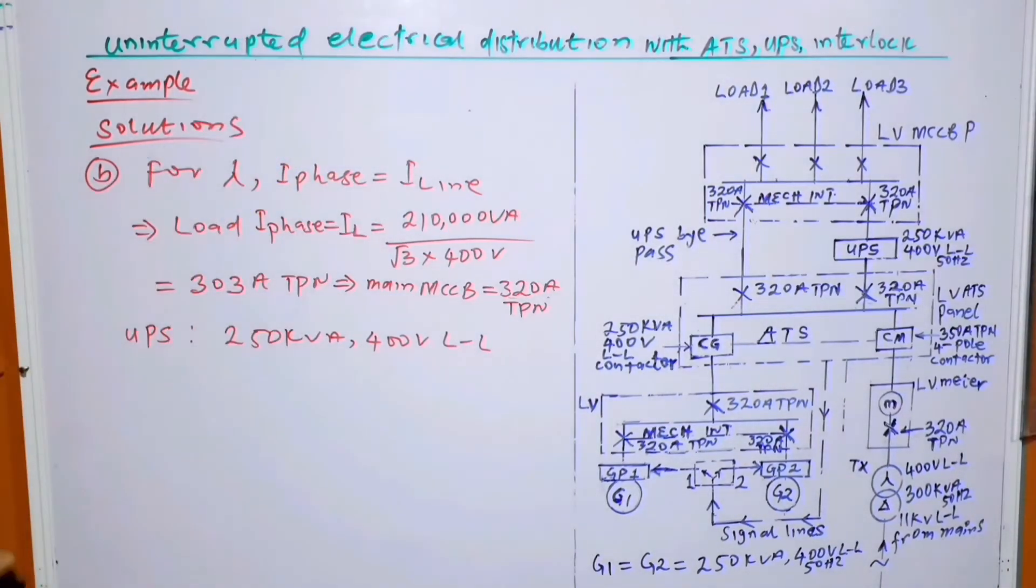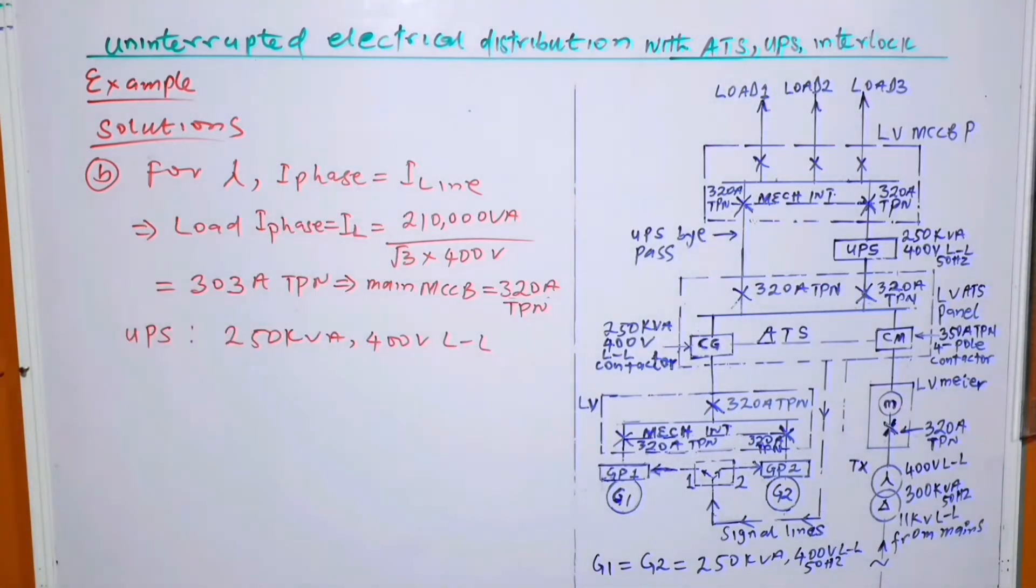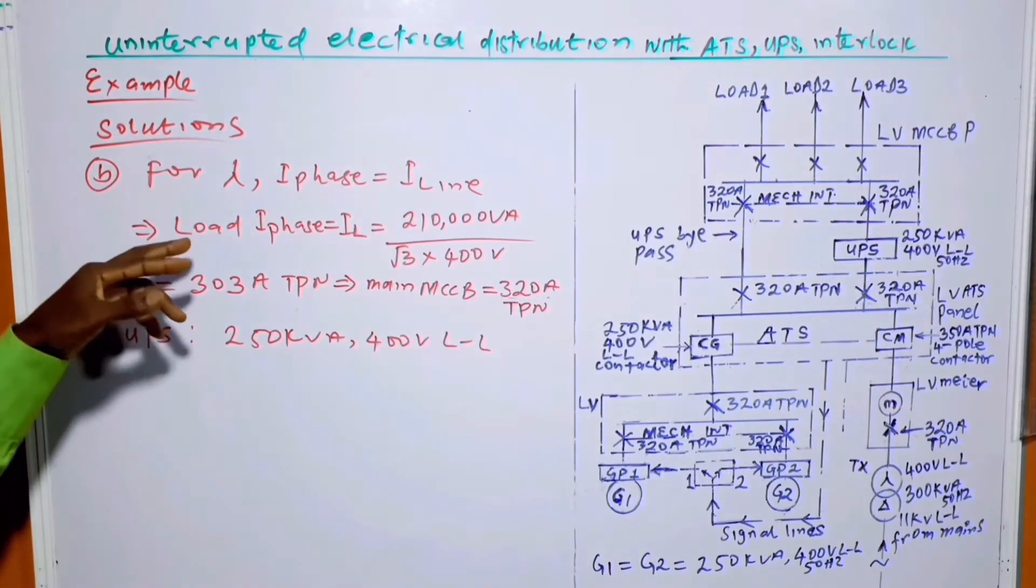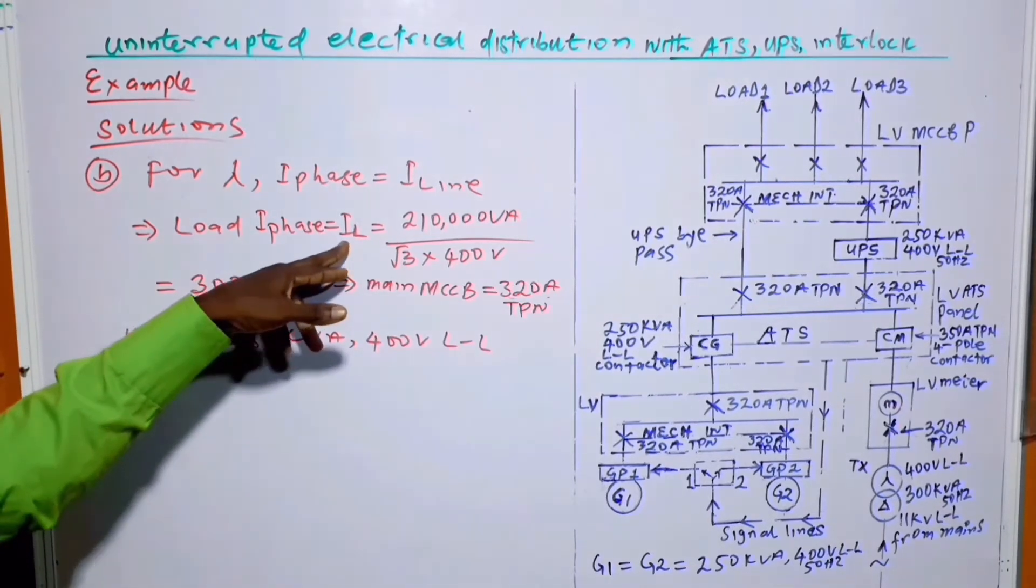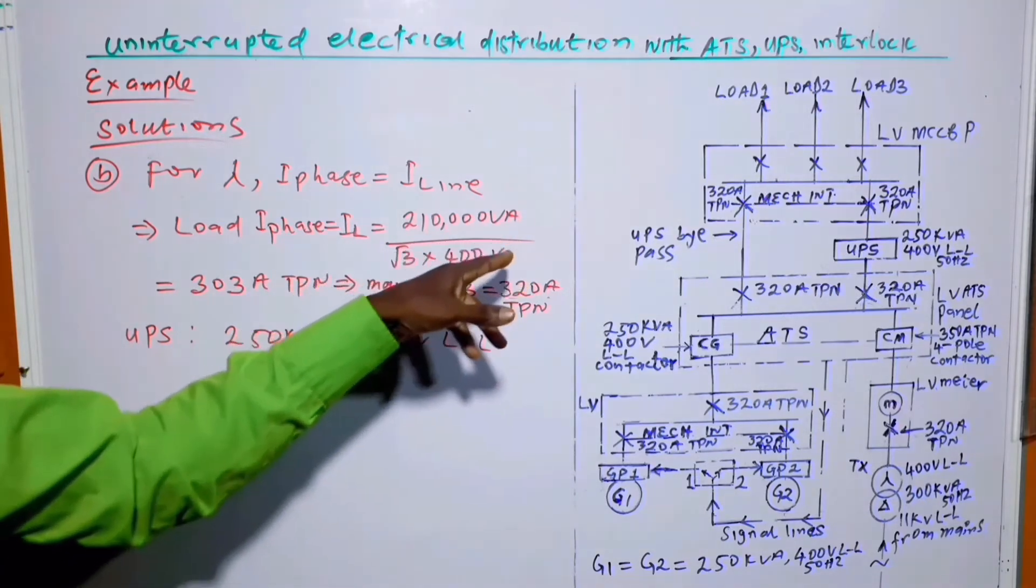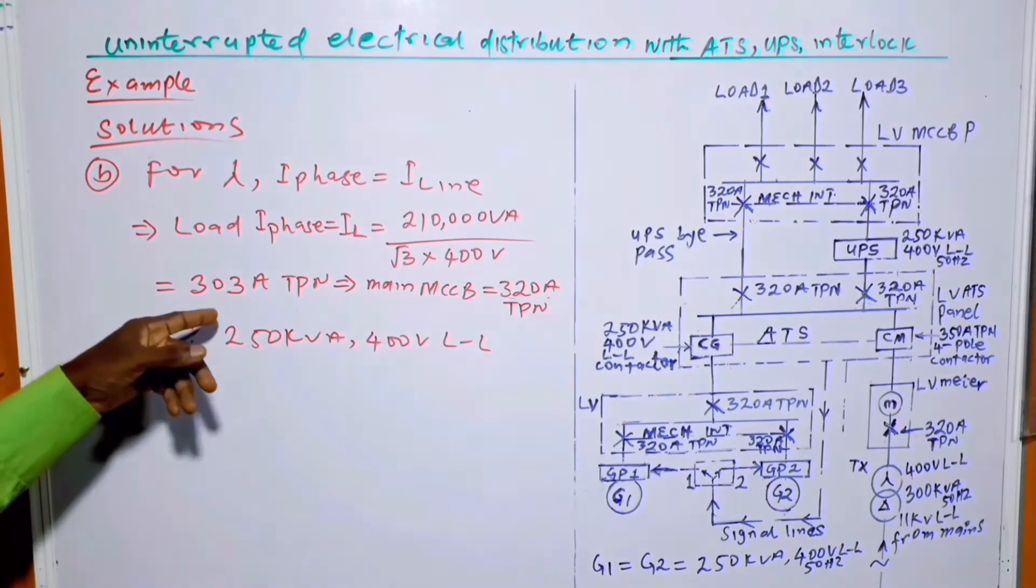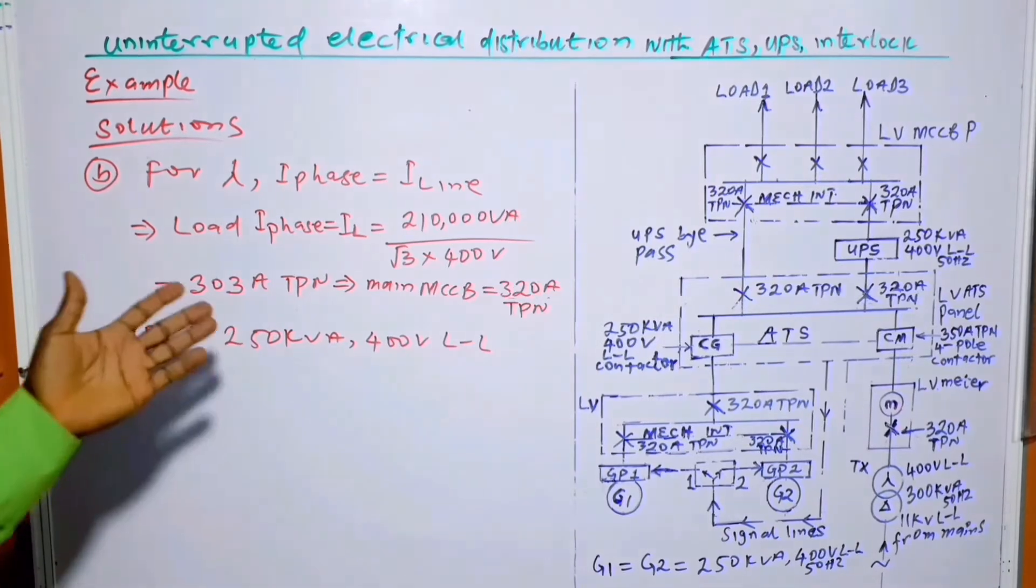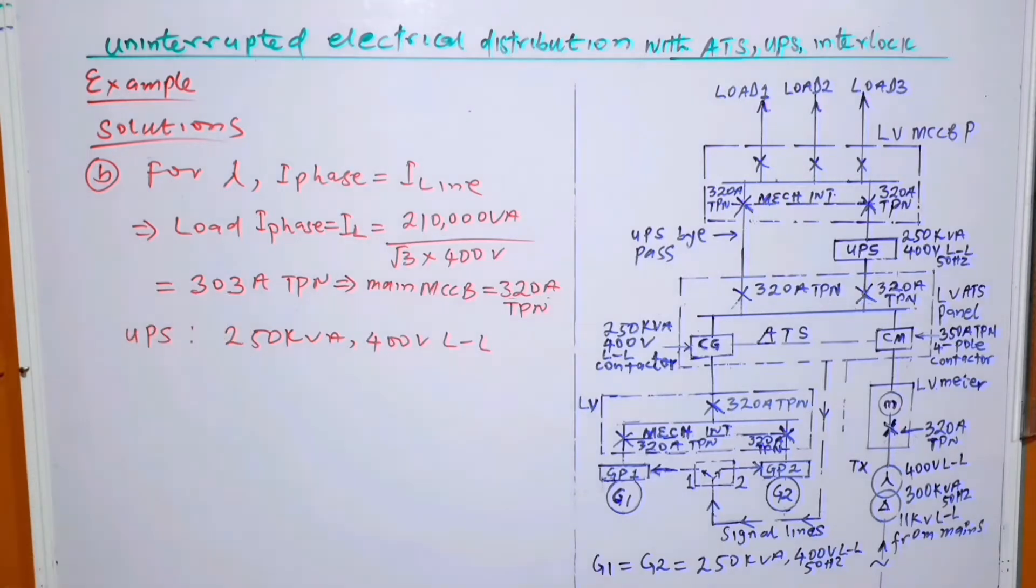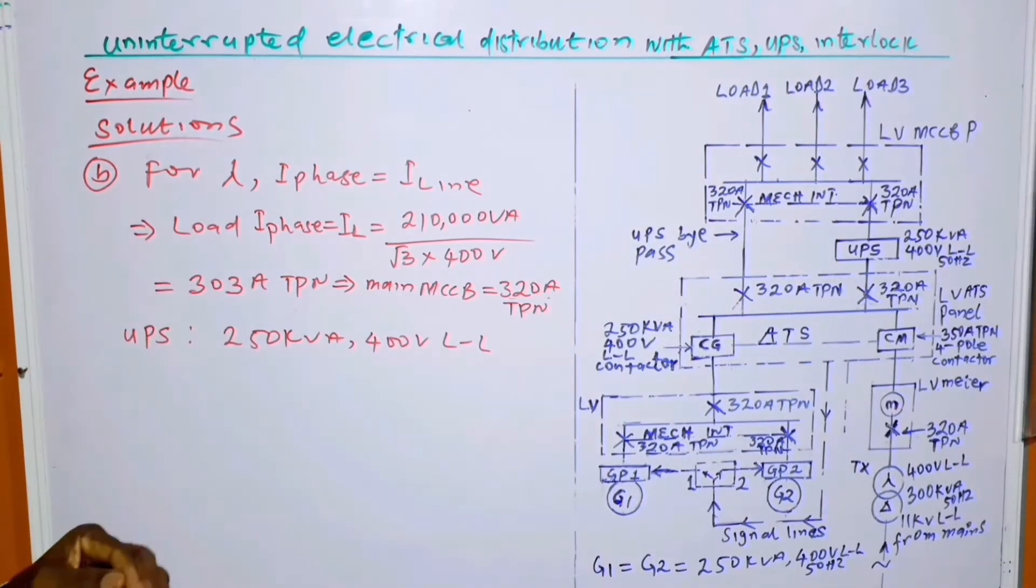Now, let's calculate the load current. For star connection, I phase equals I line. As I mentioned in one of my previous videos, the load I phase equals the load I line which is equal to 210kVA divided by root 3 times 400 volts, and that is equal to 303 ampere triple phase with neutral. It doesn't mean that the neutral current is 303. It only indicates that neutral is part of the system.